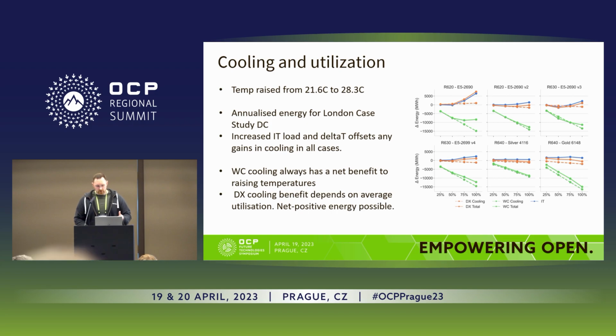When you raise the temperature from 21 degrees to 28 degrees, this is what you see. The green line is a water-chilled system. So this is the one I was talking about using pre-cooled air coming in, basically pre-cooled chilled air. And what you're seeing is in every single case, raising the temperature massively decreases the amount of energy required to cool that center. So when you take this data center in London and you make sure it's liquid, it's cooled with what we call water-cooled, so WC system, it always makes sense, irrespective of the IT, to raise the temperature. Always.